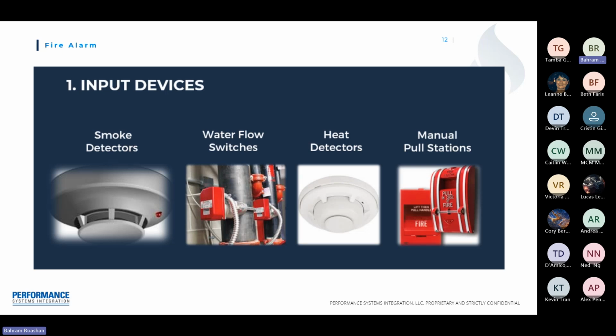Water flow switches detect when water is released in a fire sprinkler system. If the sprinkler detects heat, the sprinkler head opens up, flowing water to the sprinkler head. This in turn will tell the monitor module input device to send a signal to the fire alarm control panel communicator, sending a signal to the central station for fire department response. This too will cause the horn strobes to go off. A pull station is a manually operated device that triggers a fire alarm to alert people in a building. It also sends a signal to the fire alarm control panel and then communicates to the central station for fire department response.